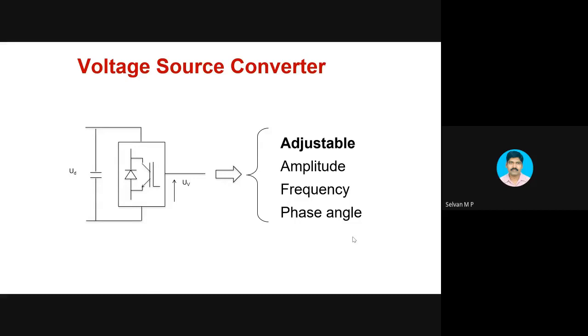Voltage source converters are capable of providing adjustable amplitude, frequency, and phase angle at their output. So, what is a voltage source converter? It is an IGBT based inverter, right? If I have a constant DC voltage, that's why it is called a voltage source. By changing the firing of these IGBT switches, which may be a 6 pulse bridge or 12 pulse bridge, which I'm not going into because, as I said, I am not going to deal with the power electronics involved, if I have an IGBT inverter, by changing the PWM, pulse width modulation, scheme, I will be able to get an AC voltage whose magnitude, that means amplitude, frequency, and phase angle can be adjusted.